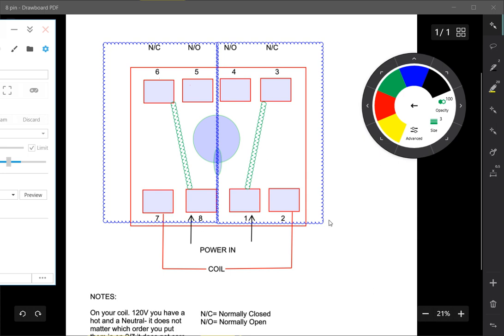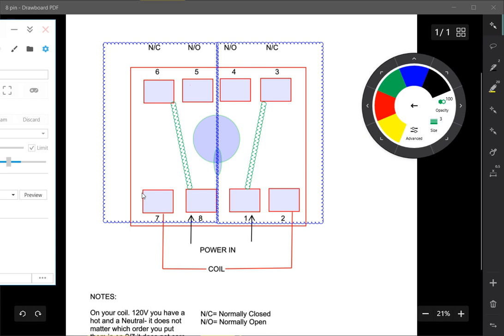So the coil being 7 and 2, in this particular case let's just say it's 120. So your hot will come in here and your neutral will come in here. I get a bunch of questions about the configuration. I just like to do left to right, it doesn't matter, it really doesn't. You can put the neutral over here and hot over here and it will work. What you can't do is just have a hot and that's it, unless it's a 240 coil then you'd put hot hot. But in any other particular case you need a hot and a neutral or a neutral and a hot. It doesn't matter which way it goes on the thing, it doesn't care.